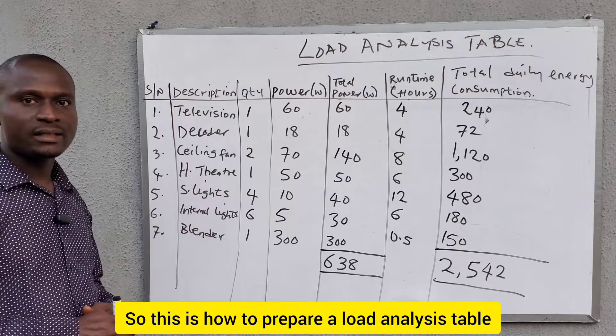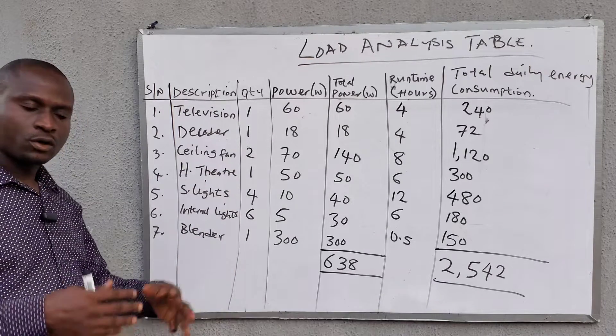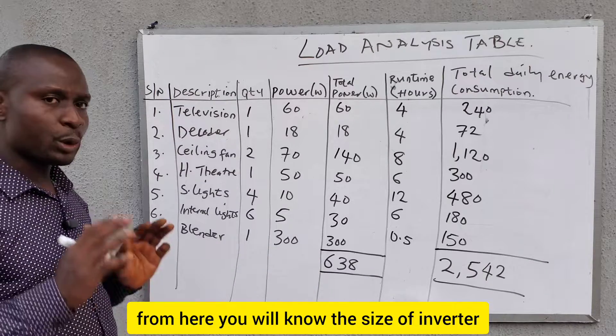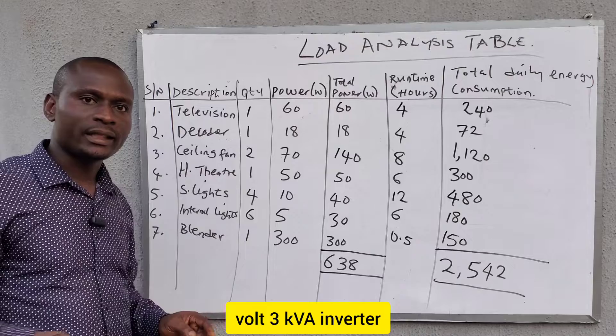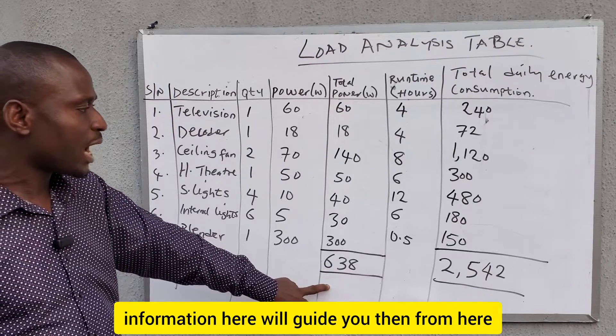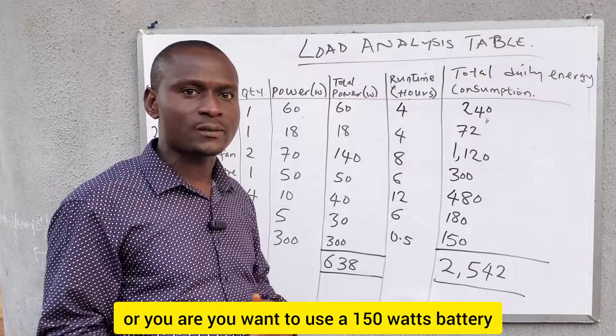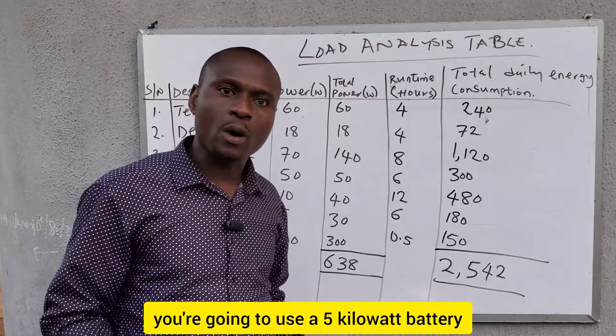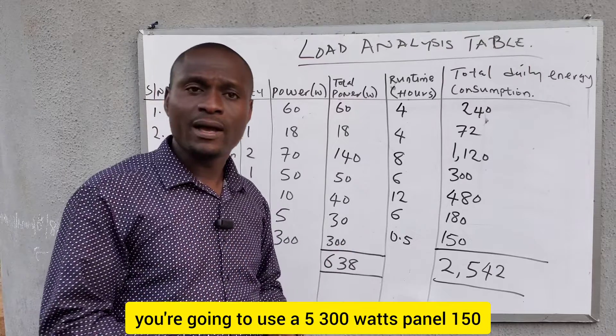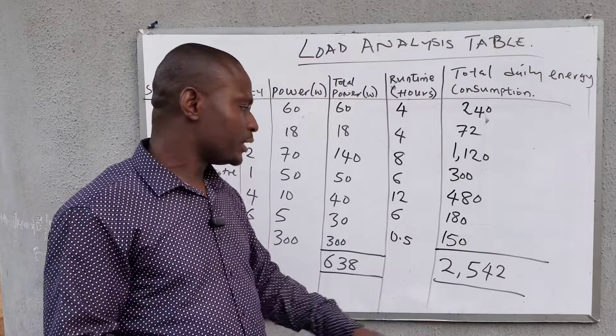This is how to prepare a load analysis table. Whenever you go to a client's house, always bring a notepad and a pen so you can gather all this information. When you come back, you work through it and from here you can size all the components — you'll know the inverter size to buy, whether a 24V 3 kVA or 24V 2.5 kVA inverter, and you'll know whether to use 200 Ah batteries or 150 Ah batteries, or for lithium batteries whether to use a 5 kWh, 2.5 kWh, or 10 kWh battery. You'll also know how many panels to use — whether 300 W, 150 W, 100 W, 350 W, or 500 W panels.